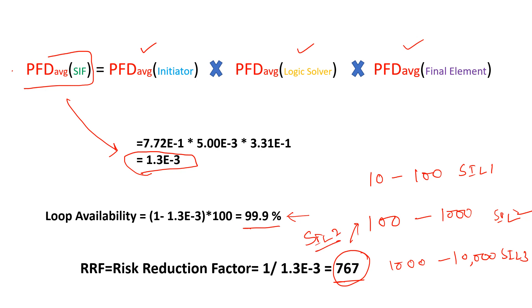However, there are two other things to consider before declaring the loop as SIL 2: hardware fault tolerance (HFT) and systematic capability. Depending on these, the final SIL declaration could be SIL 1, 2, or 3. Using this simplified Markov analysis approach, you can calculate the SIL level entirely in Excel without sophisticated software like Exsilentia or SIL Solver. Try it on your own and verify your calculations — for any doubts, feel free to write to me.